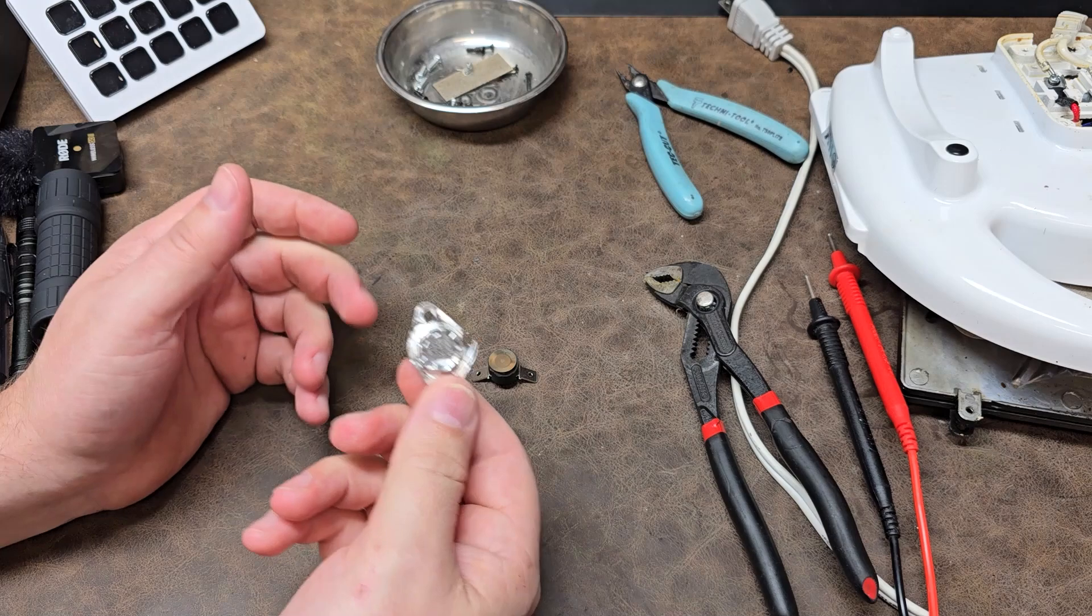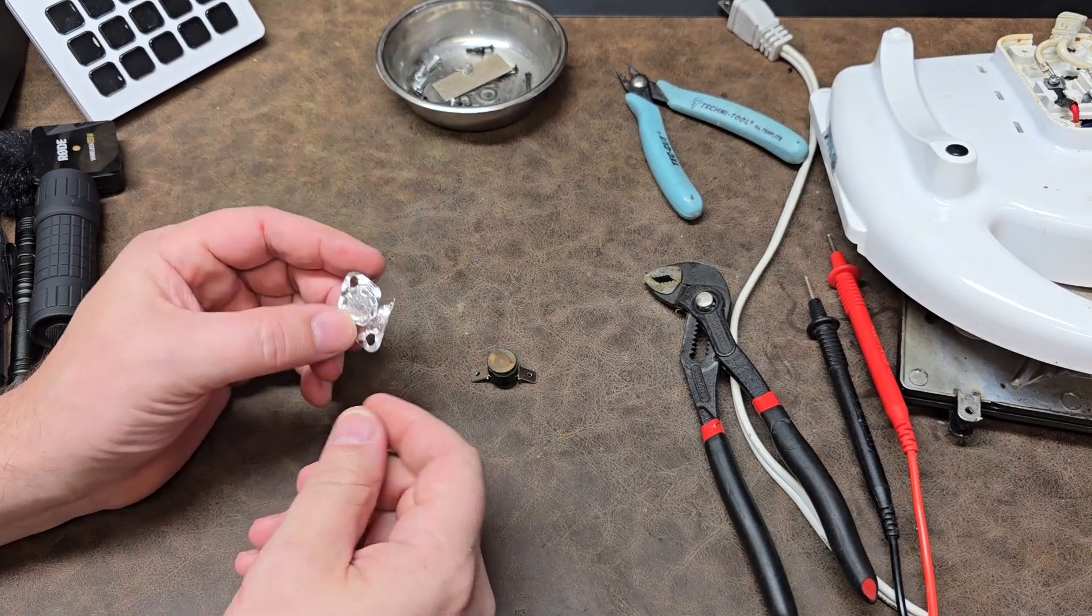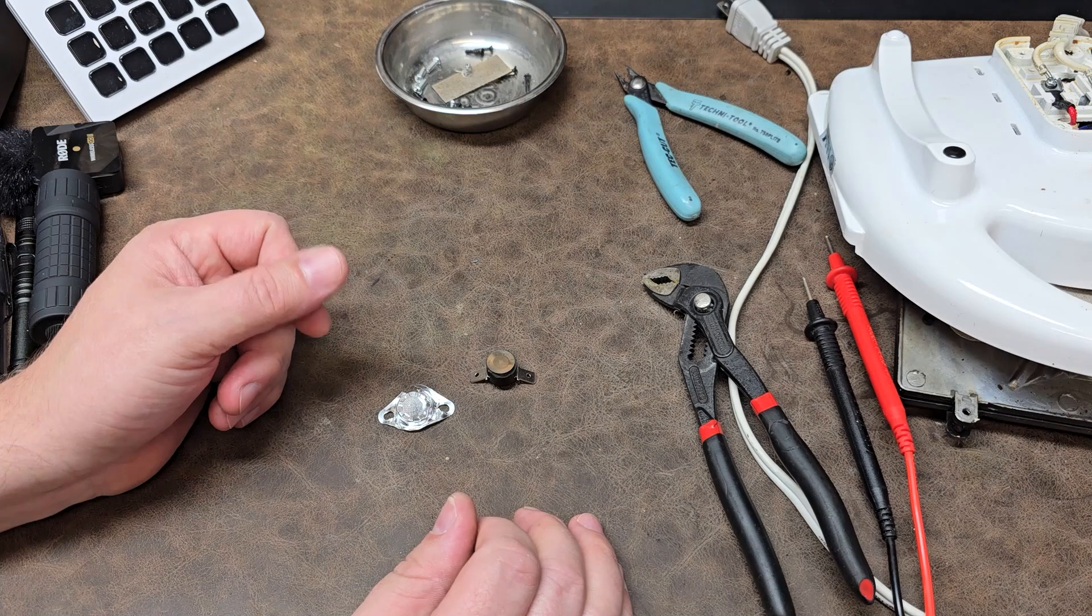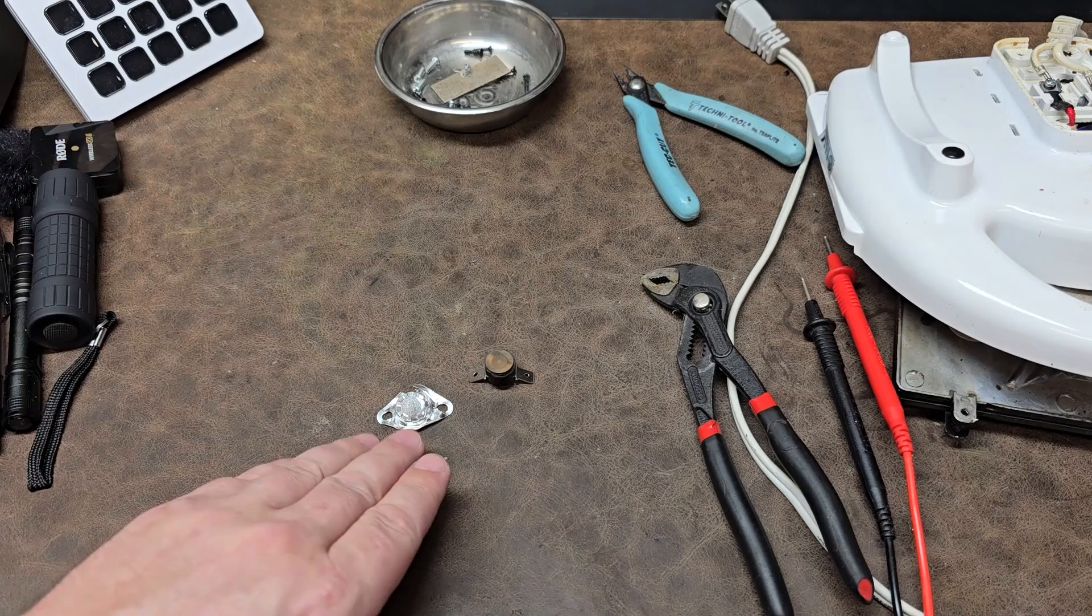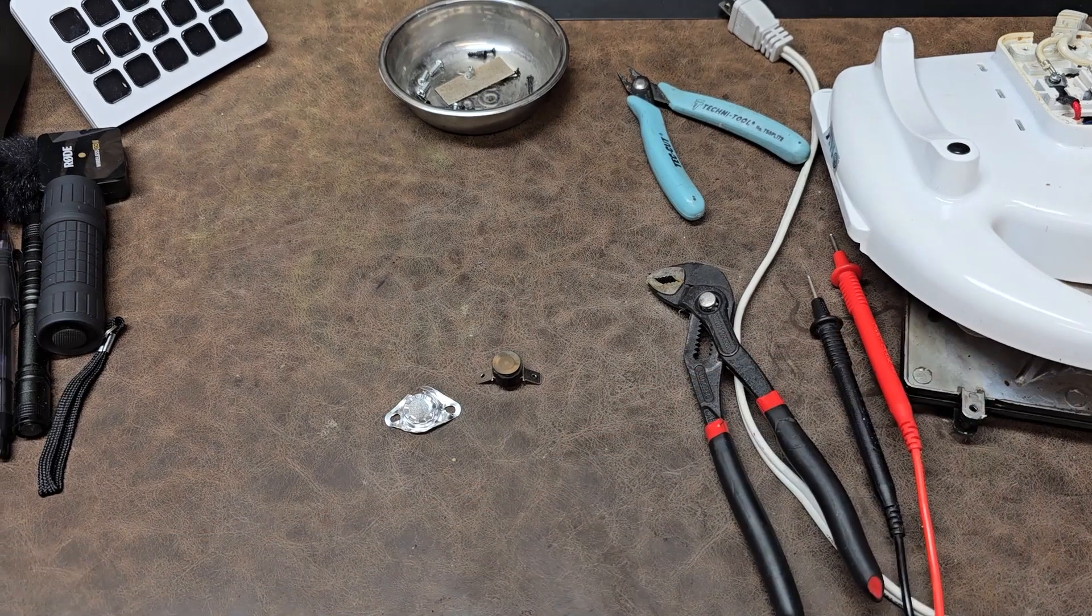This here is a device that when it gets to a certain temperature it disconnects the electricity that goes to the heating element, and as it cools off it resets automatically with no intervention from the user and it allows it to maintain a very consistent temperature. So it clicks on, clicks off, clicks on, clicks off, and by doing so, whatever the calibrated temperature is of this guy right here, that is the temperature that your device is going to run at.